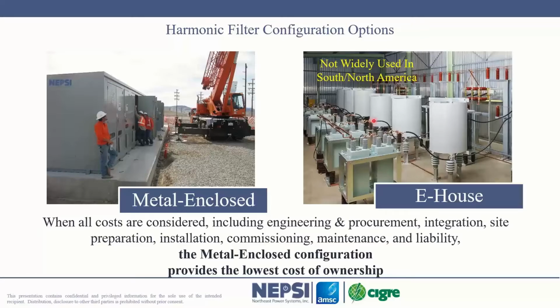Dan Martin asked, do you find that the same harmonics are always there so that the filters can be tuned and left, or do the harmonics change throughout the day and thus the filters need to be adjusted? That's a good question, Dan. What Dan's asking is, are the harmonic currents in the network changing throughout the day? If so, do we need to make changes to the filter systems on a day-by-day basis?